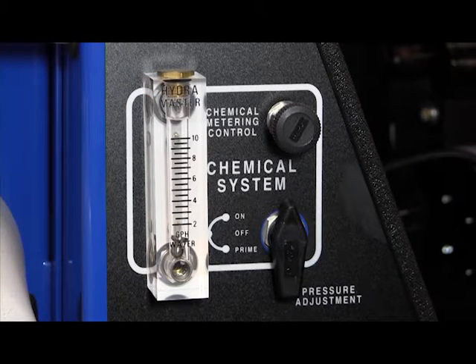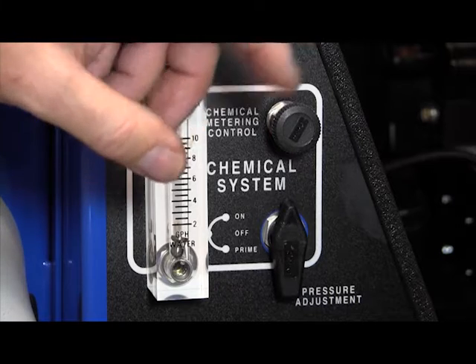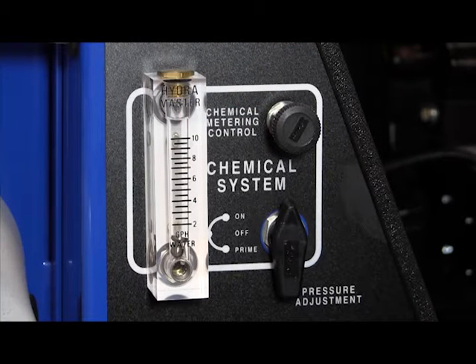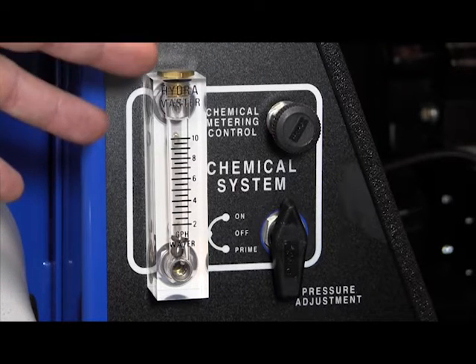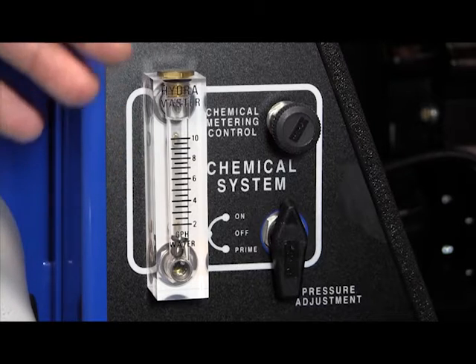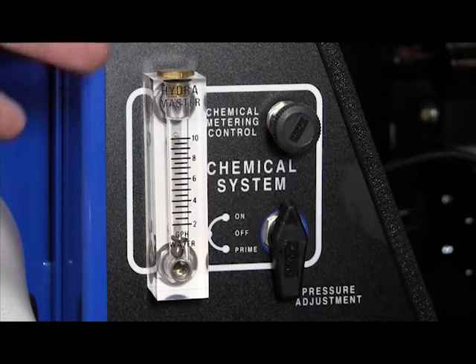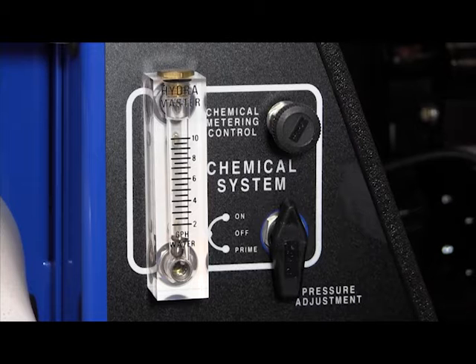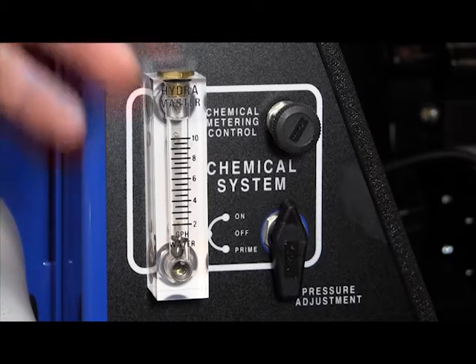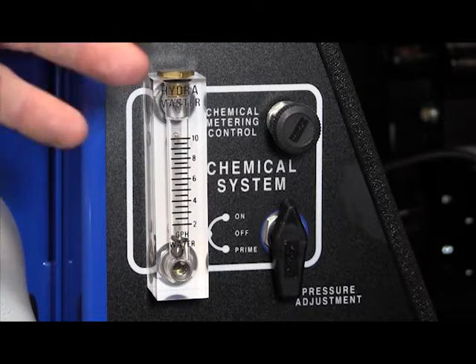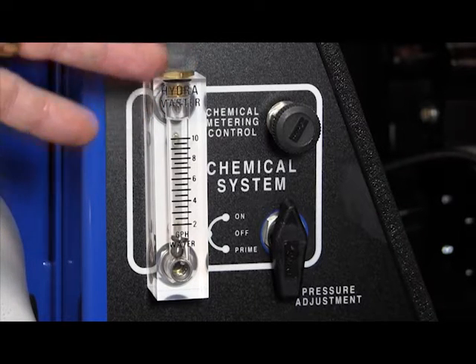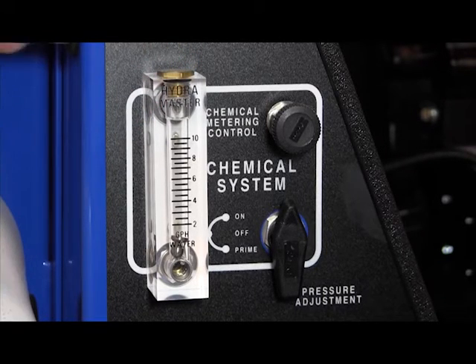We use what we call the last step chemical pump, attached to the pump itself. The injection of chemical is done after the water has gone through our system and heated, so no chemical is added into the system to degrade any fittings, depending on whether you're using an acid or alkaline type cleaner. We're trying to minimize exposure inside the equipment to make it last, since it's a big investment.